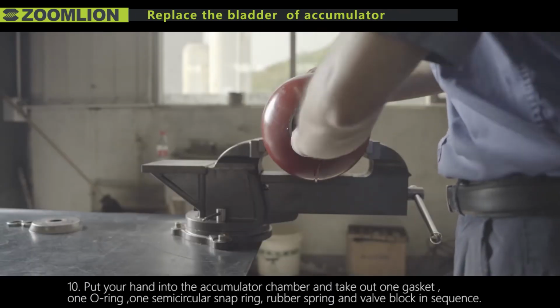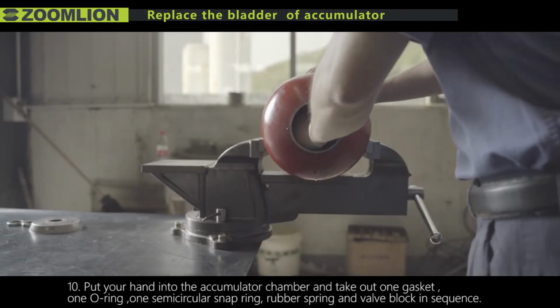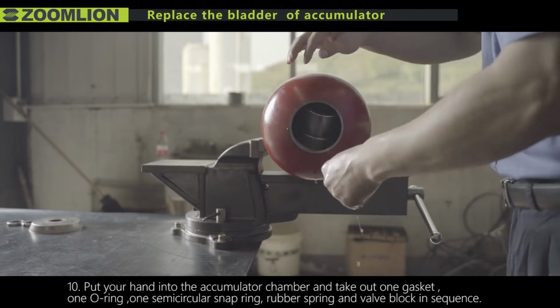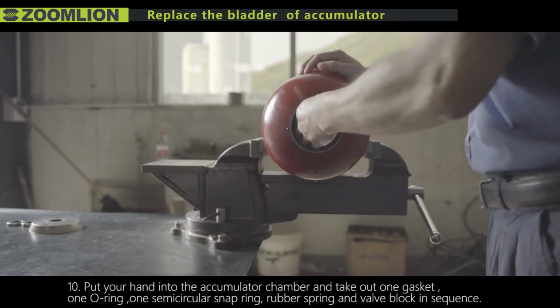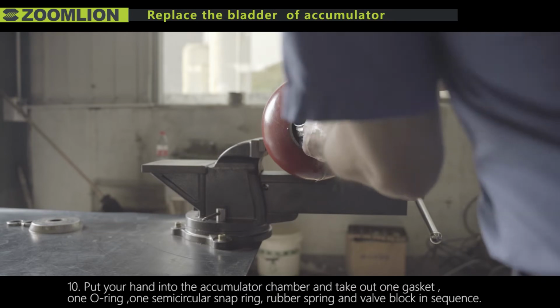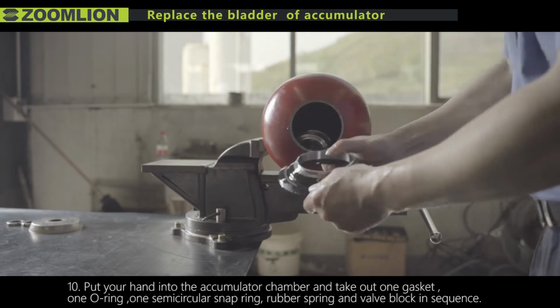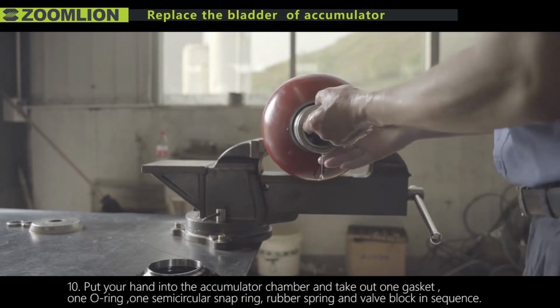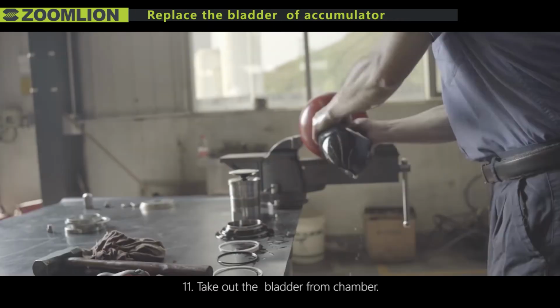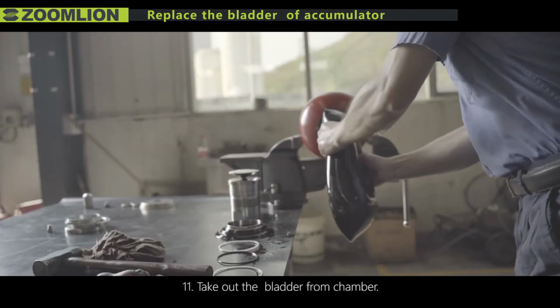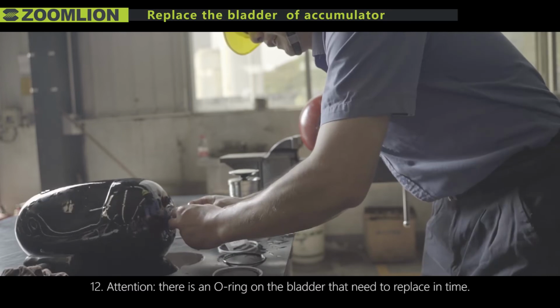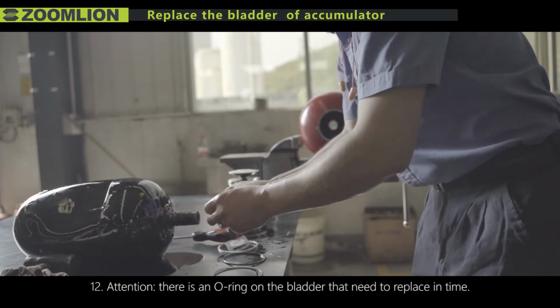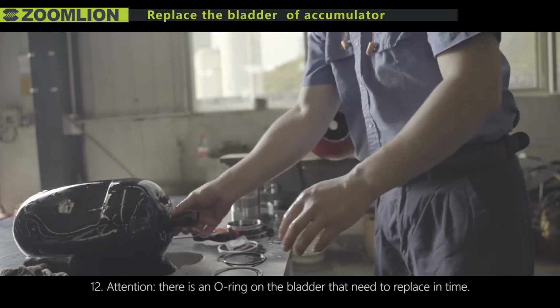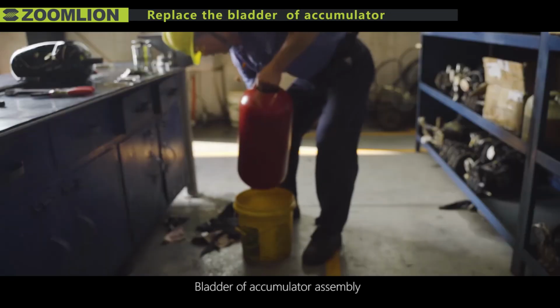10th, put your hand into the accumulator chamber and take out one gasket, one O-ring, one semicircular snap ring, rubber spring, and valve block in sequence. 11th, take out the bladder from chamber. 12th, attention! There's an O-ring on the bladder that needs to be replaced in time.